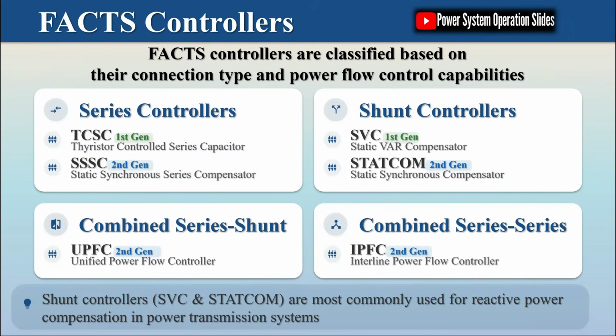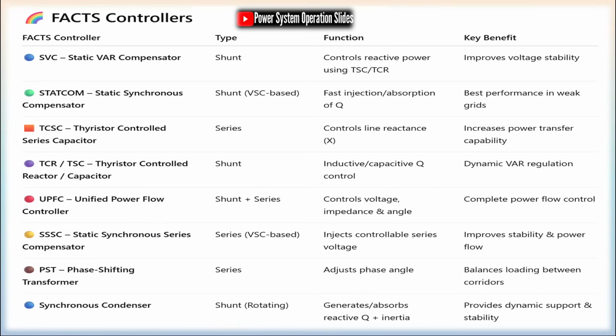Instead of varying impedance, a STATCOM acts as a controllable voltage source that can generate or absorb reactive power by controlling the voltage difference across the coupling transformer. When the STATCOM's output voltage is higher than the system voltage, it supplies reactive power to the system. When it is lower, it absorbs reactive power. The reactive power output of a STATCOM is directly proportional to the system voltage. Q is proportional to V, rather than the square of the voltage as in an SVC.